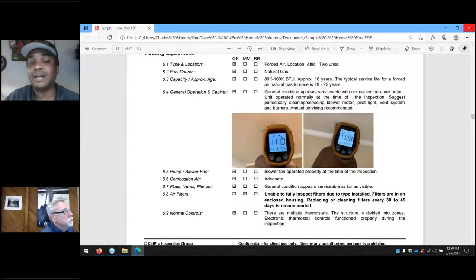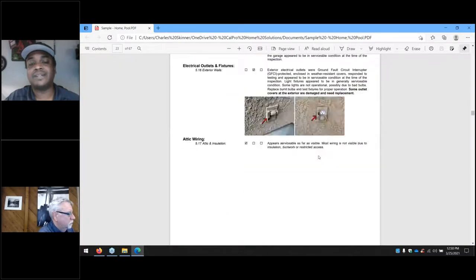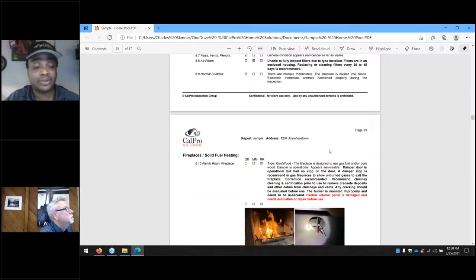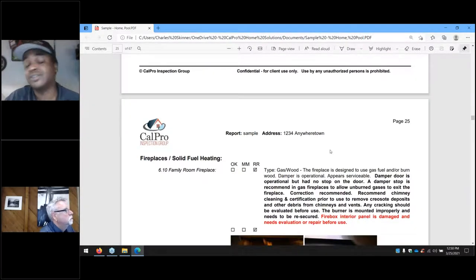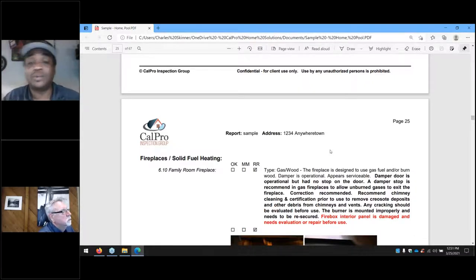We check temperature differential between the supply and the return. As long as it's somewhere between 18 and 20 degrees, that's considered normal. We operate the equipment on the day of the inspection. We'll do our best to identify problems that may become a problem in the future, but it's not always possible to know. We'll go in and inspect a water heater that was perfectly functional on the day we were there — it's an older unit, maybe 10 to 15 years old, works fine — and then it fails within a week or two after we're there.